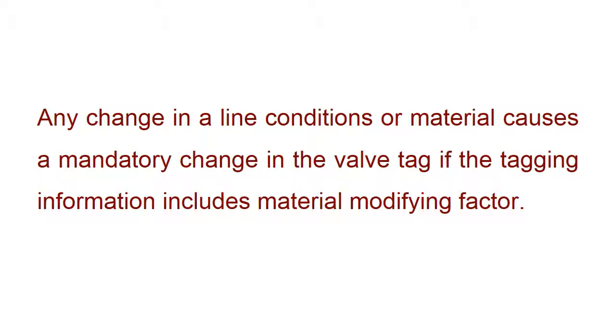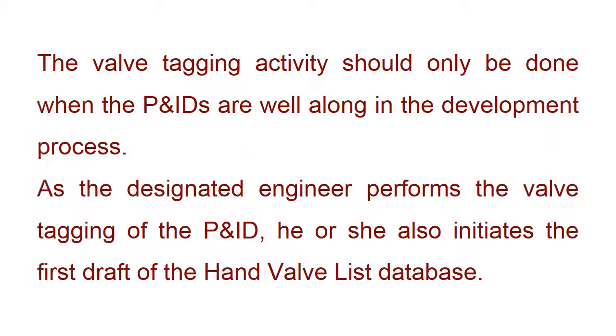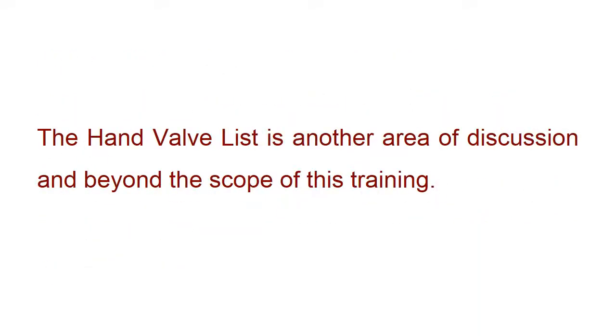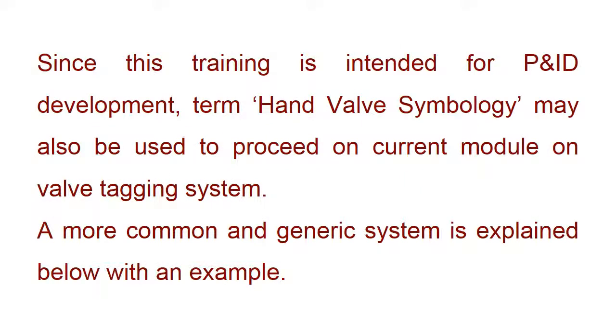Any change in the line conditions or material causes a mandatory change in the valve tag, if the tagging information includes a material modifying factor. The valve tagging activity should only be done when the P&IDs are well along in the development process. As the designated engineer performs the valve tagging of the P&ID, he or she also initiates the first draft of the hand valve list database. The hand valve list is another area of discussion and beyond the scope of this training.